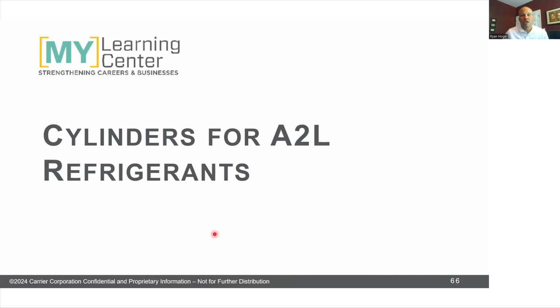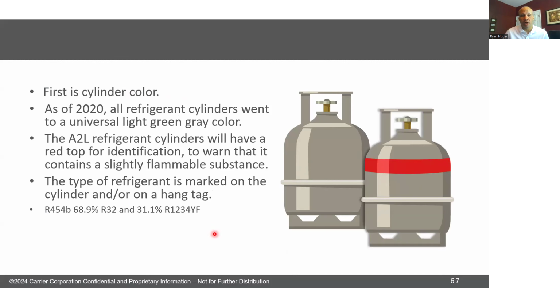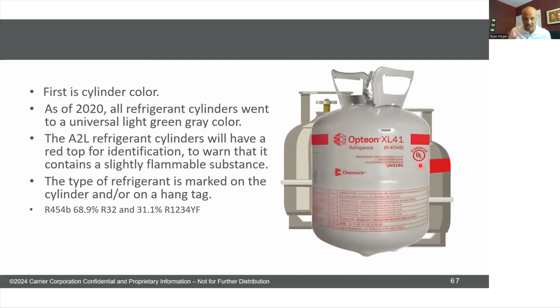All right, from the cylinder perspective, as you probably know, all our refrigerant cylinders changed to gray. We used to have nice colors before, pink for R-410A, for example, and that all went away. I have no idea why. We can't do colors anymore. I don't know if Crayola got upset and shut it down or whatever, but everything's gray. A2Ls are also gray, but now they're gray with a red band on them. So regular gray is an A1, gray with a red band means it's flammable. And it'll still have all the markings and the verbiage and the branding on here.